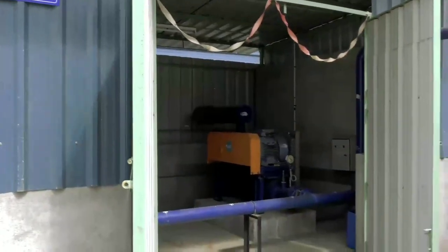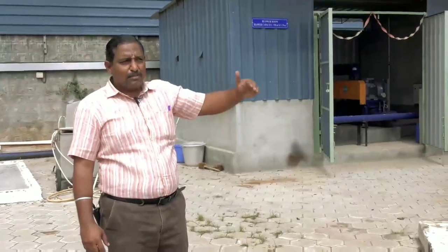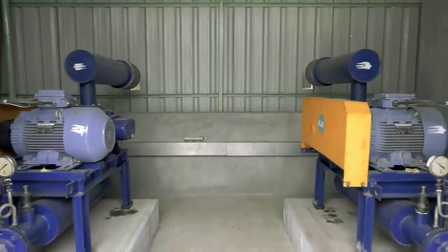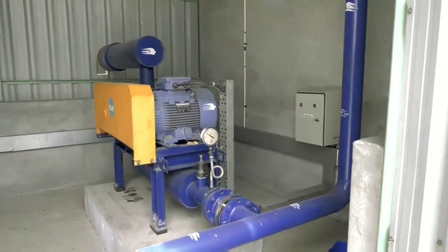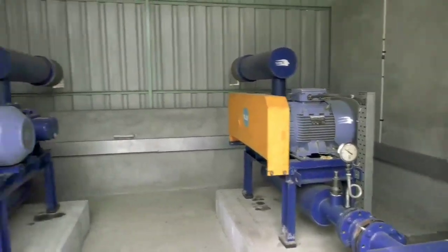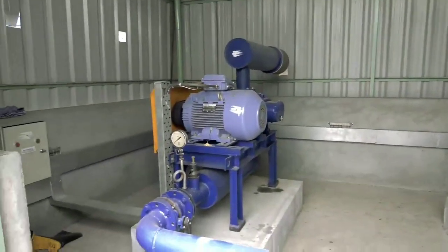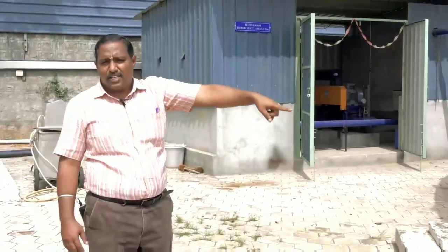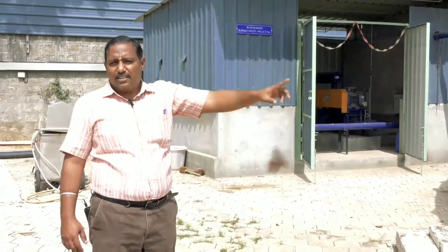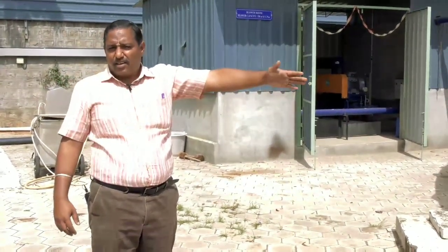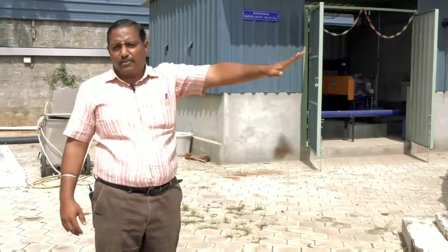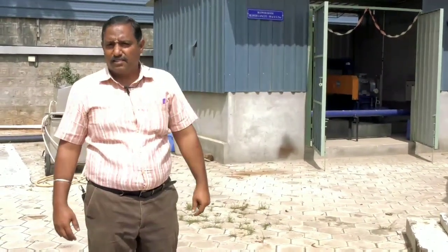All of this needs some technical calculation, and based upon the calculation, we are fixing the optimum amount of air required for effective treatment inside this aerobic chamber. After that technical data, we are fixing the capacity of the blower or compressor, by which the optimum air is sent into the reactor, whereby the organisms get optimum dosage of air or oxygen, and it enables effective treatment inside this aerobic treatment chamber.